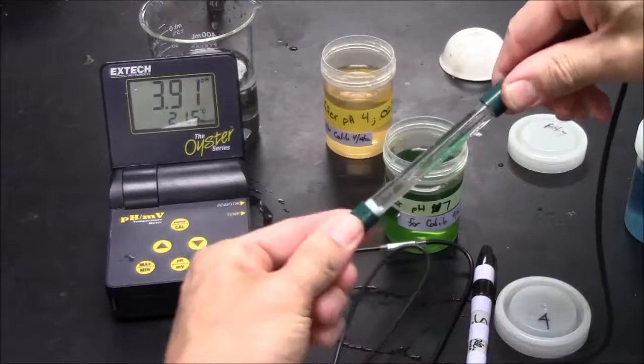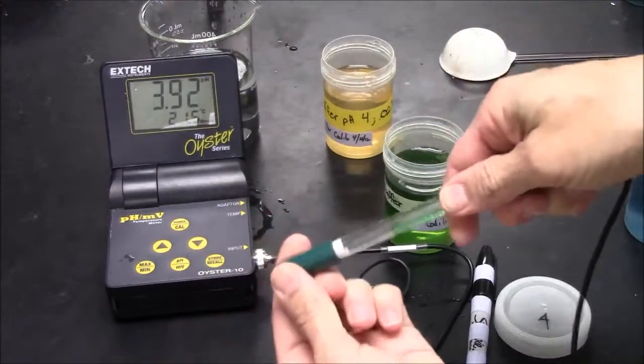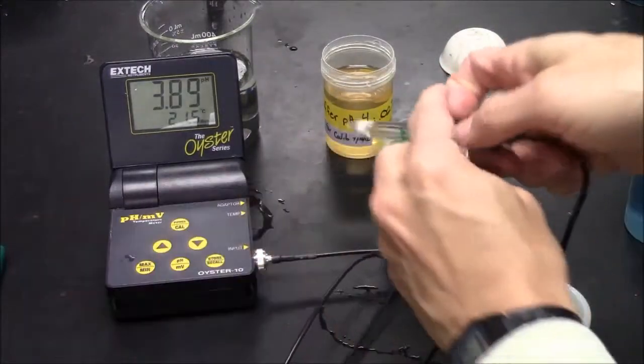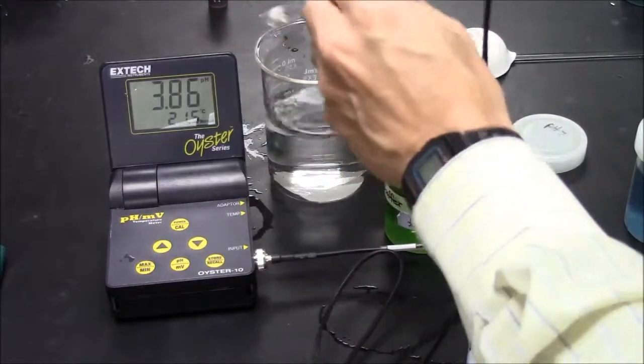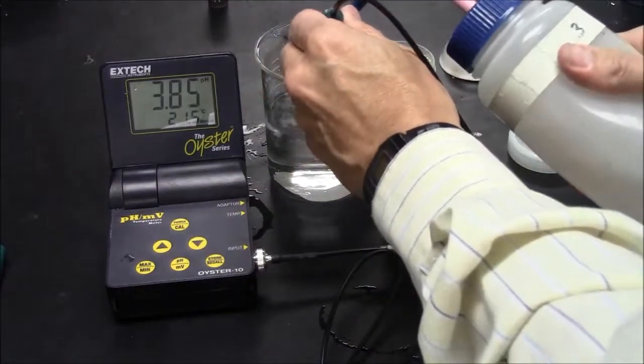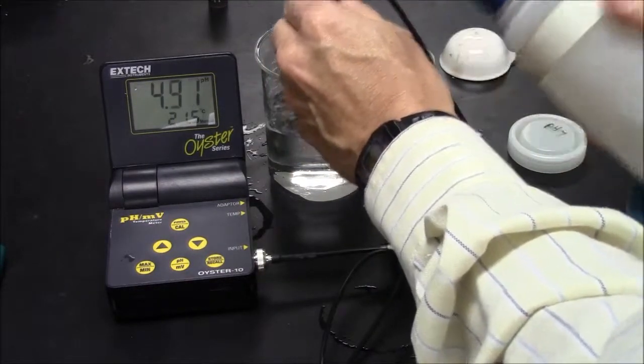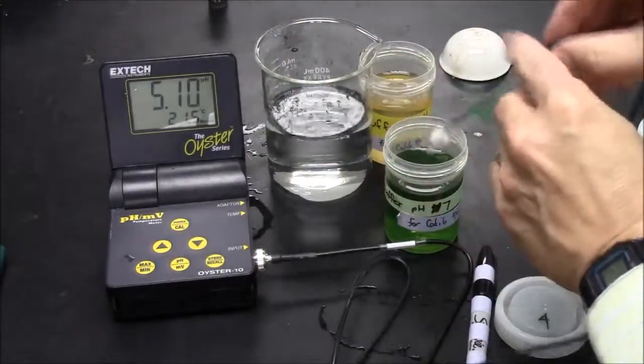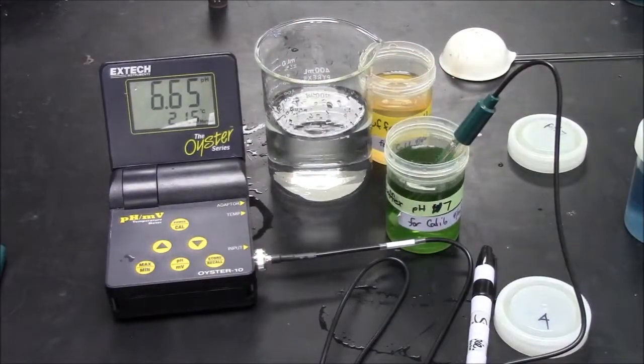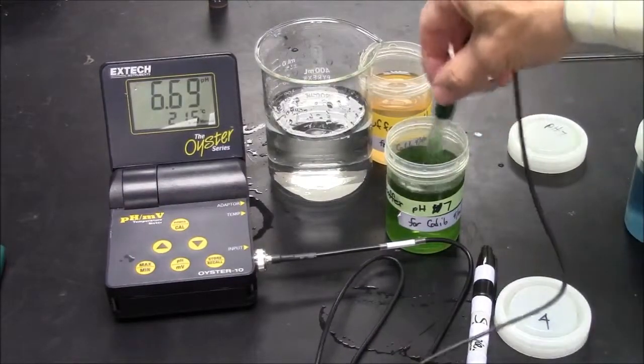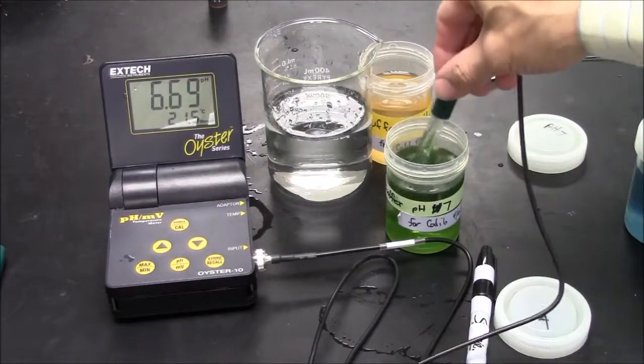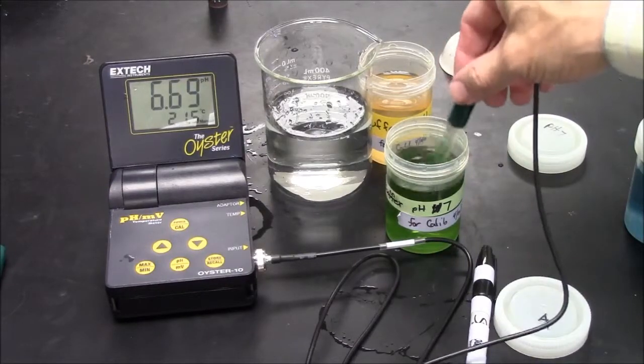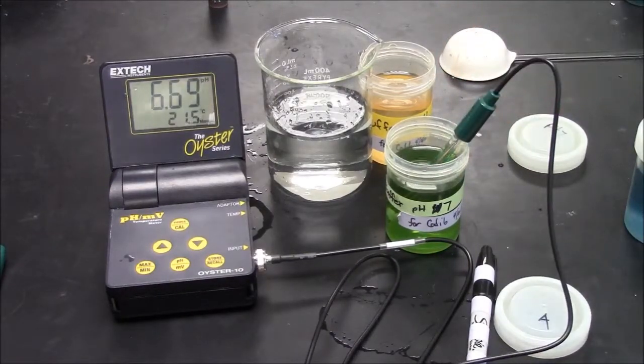I will rinse the, well, first I remove the cap. Then I will rinse off any material that's on the electrode into a waste beaker. Then I will immerse the electrode in pH 7, and I'm looking at the numbers, waiting for a stable reading. This will take about a minute or 2, so don't rush this stage if you're trying to accurately calibrate the meter.